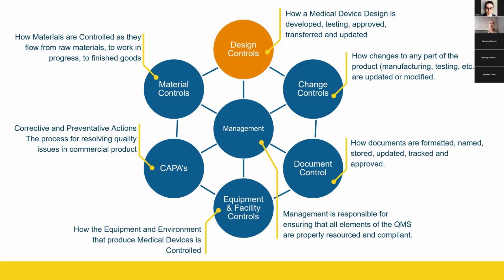You also have something that's called a CAPA, corrective and preventative actions. So this is the process for resolving quality issues. Every time you need to make a change, every time something goes wrong out in the field, a device breaks, you find out afterward the wrong material was put in a product, the wrong label was put on, CAPAs are the way that you control how you respond to and manage those kinds of things.